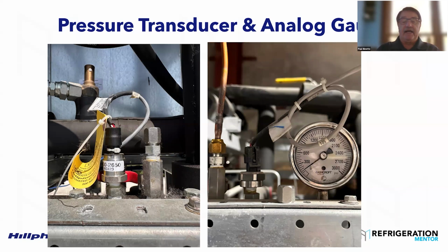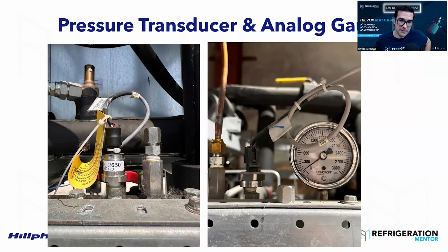Yep. One thing I like to do, when we have 150 pounds of pressure prior to startup, or whatever the contractor put on, even if it's 200, is go through every controller, look at them, and make sure all the transducers are reading. This is a good time to find out which transducers are reading and which ones are close. Because if all of them are at 200 and one's at 75, you've got a problem, and you need to look at it before you start the system up. Yeah, and I've heard this from a lot of field startup people. A lot of technicians want to get the gas in right away, where the CO2 goes in quick. It's all the pre-planning before the CO2 gets in there, before the field startup guy comes from the manufacturer, because the biggest process is doing all these checks, because there are sometimes thousands of temperature and pressure probes in a system. Could be.